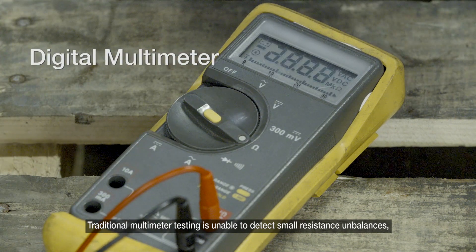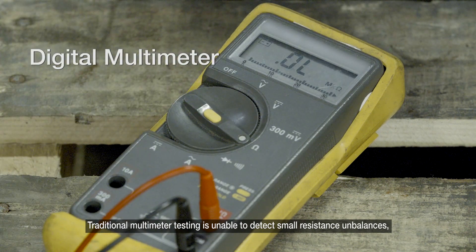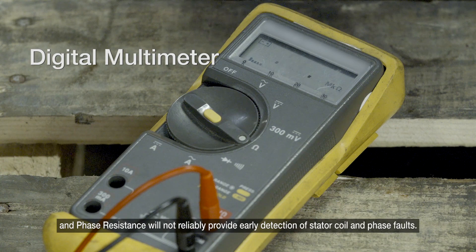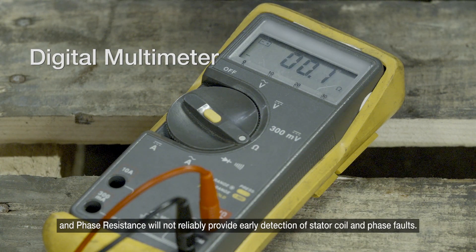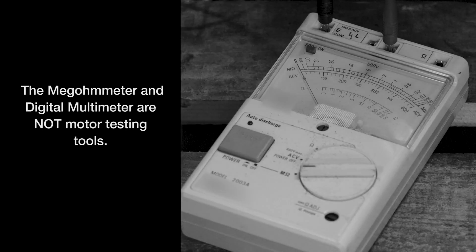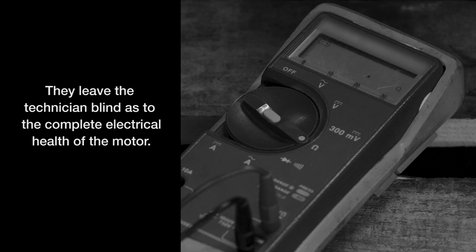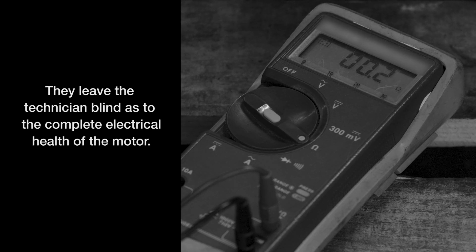Traditional multimeter testing is unable to detect small resistance imbalances, and phase resistance will not reliably provide early detection of stator coil and phase faults. The megohmmeter and digital multimeter are not motor testing tools. They leave the technician blind as to the complete electrical health of the motor.